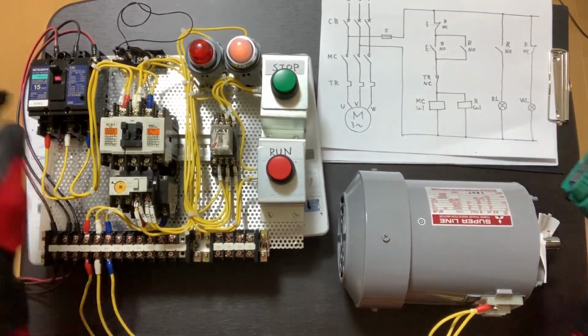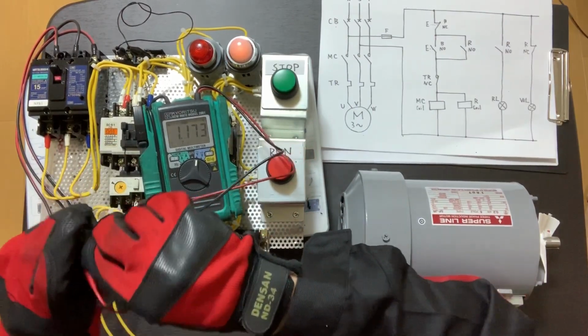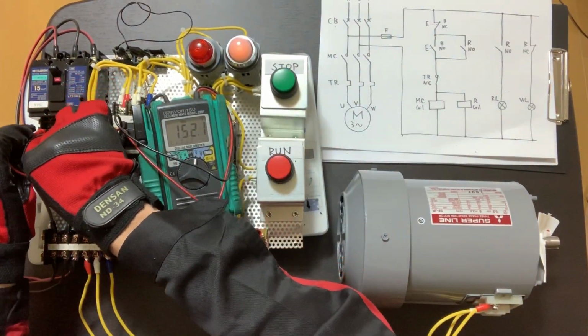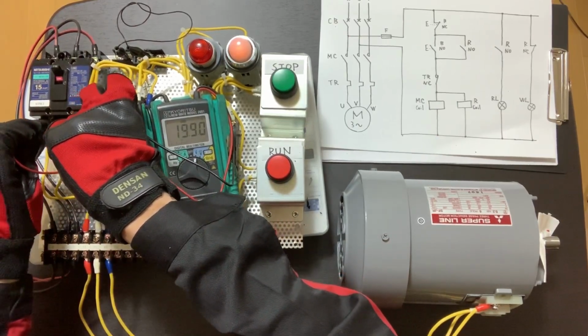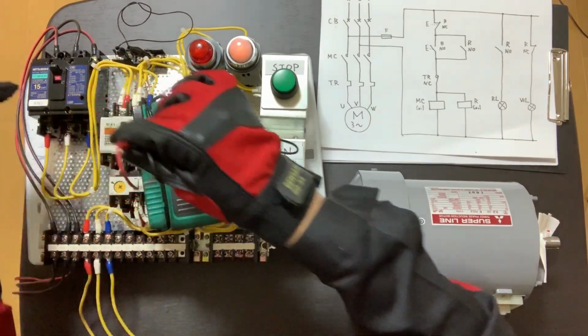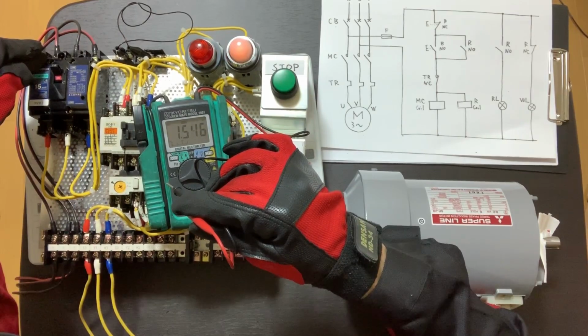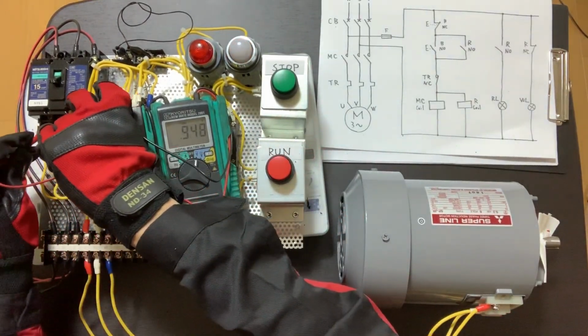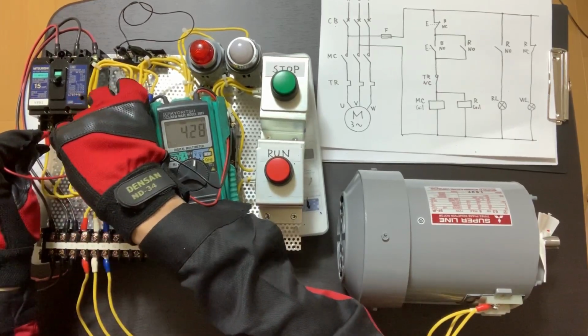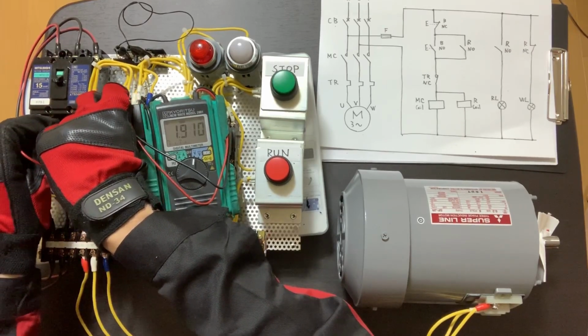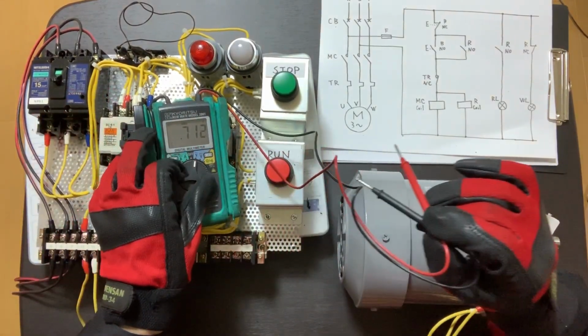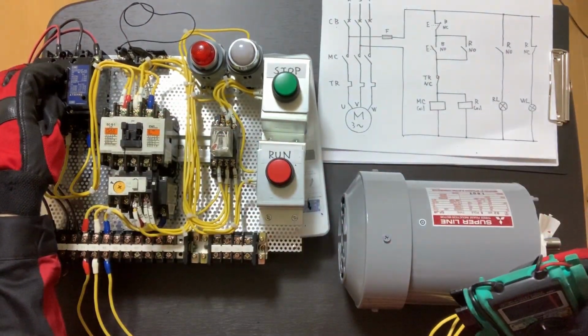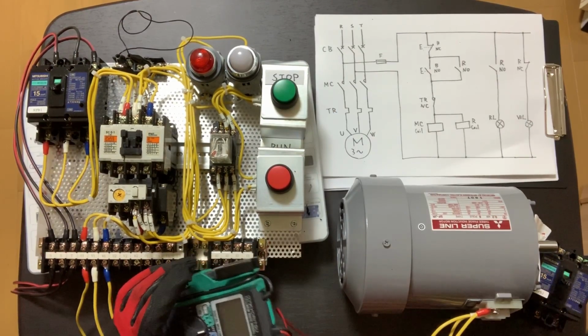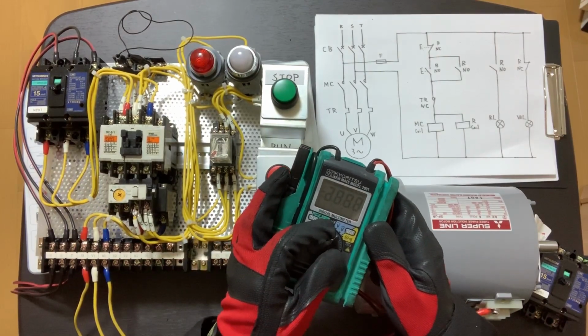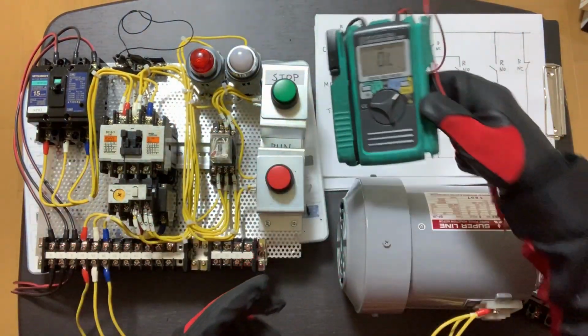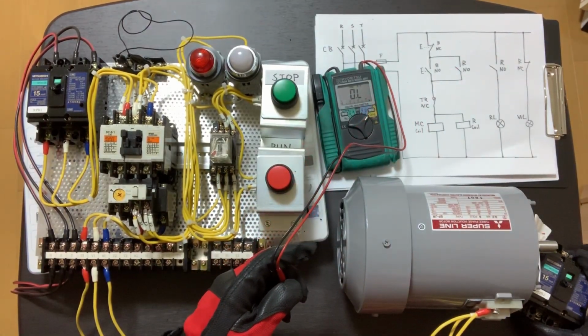So in the on state, the secondary side is 200 volt, 200 volt, and 200 volt, almost. It's the same as the primary side, just as I mentioned, I checked. But in the off state, it's 0 volt. Yeah, almost 0 volt. So it's interrupted. You can confirm the state of the circuit breaker by using a multimeter on the resistance range, even if it's not connected to a power supply.